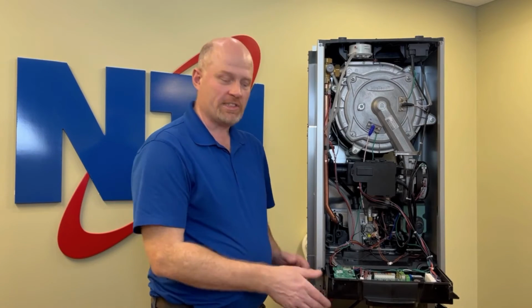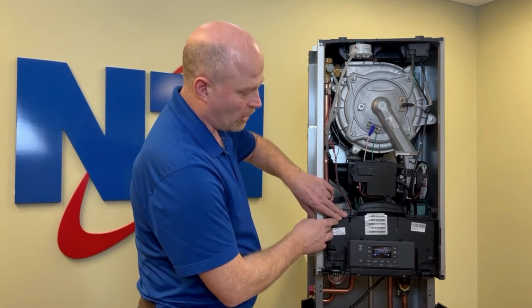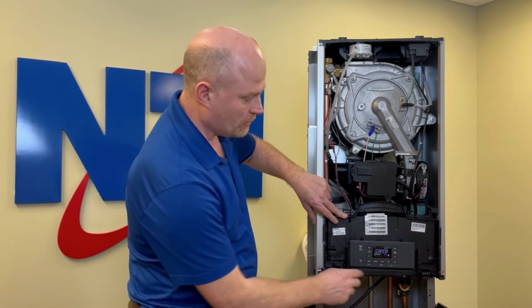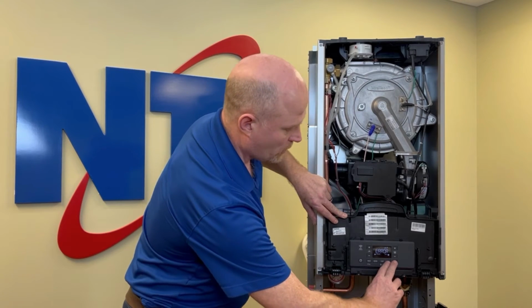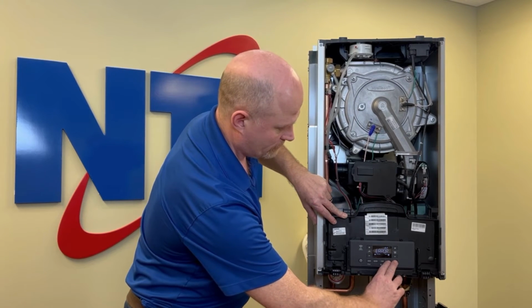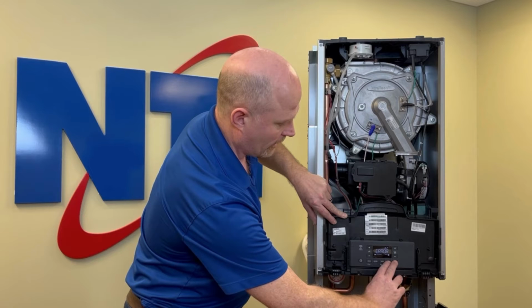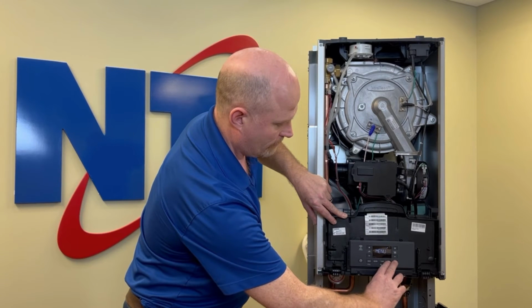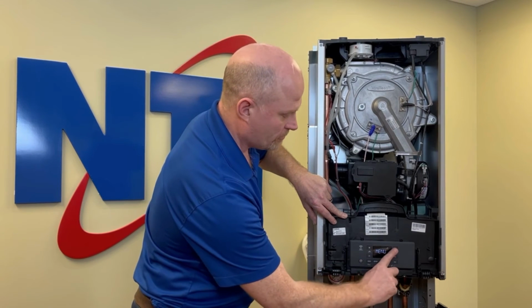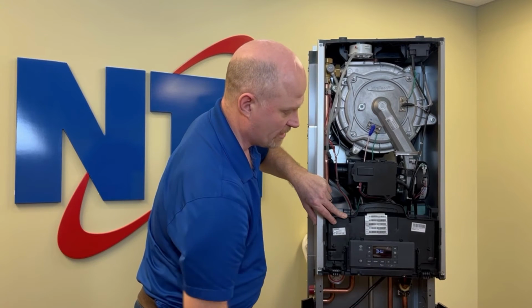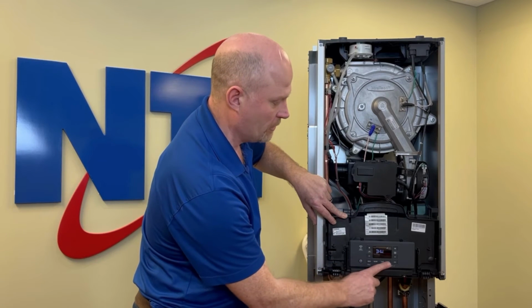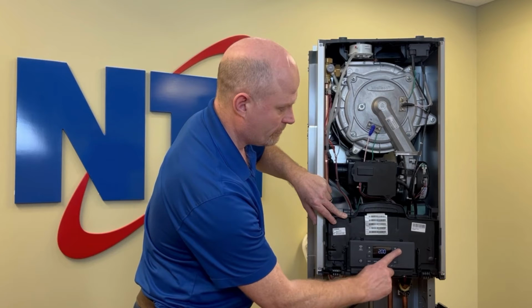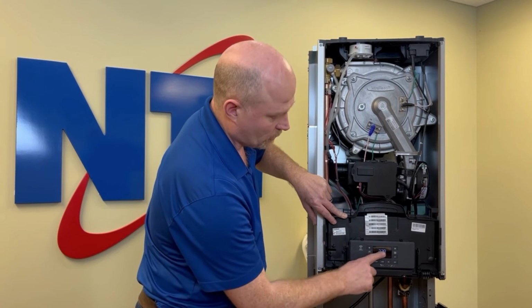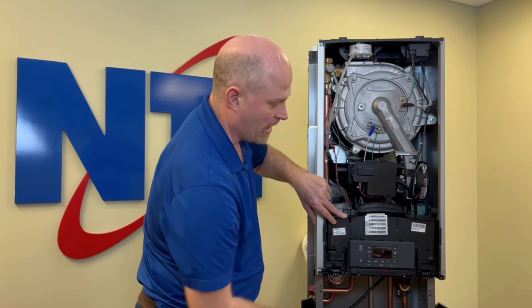If you're using an aquastat, you'll want to change your domestic hot water mode. To do that, press and hold OK and escape at the same time. Once you get to the menu, press the plus button until you see DHW, press OK, hit the plus button to go to menu 228 and hit OK again.